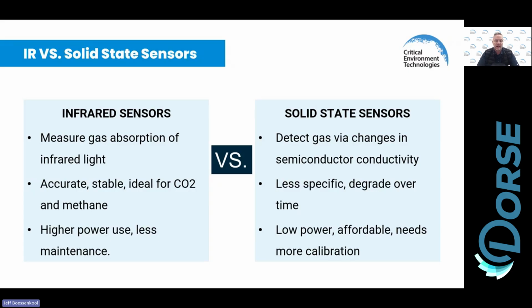These individual sensor transmitters are field configurable, which means we can configure them to communicate via Modbus, which is the native communication, or we can select BACnet. So we can have this individual sensor live on a third-party DDC system, okay, and have it communicate via BACnet to that third-party DDC system and have that system turn on the fans as well. I would say that's a less common design.